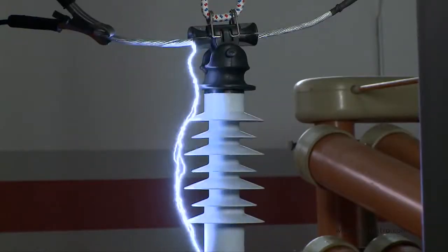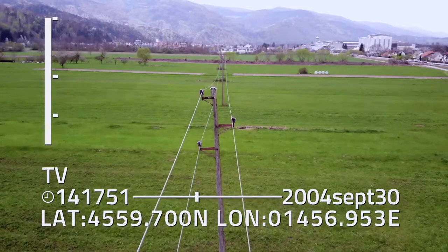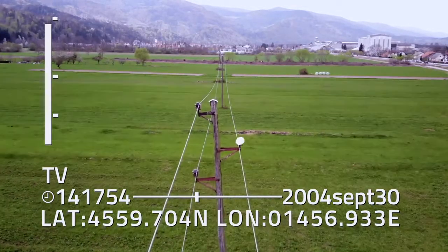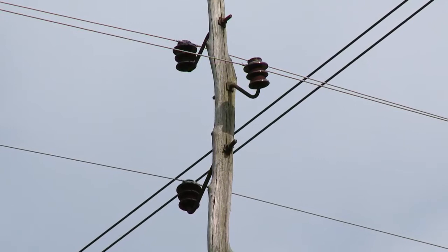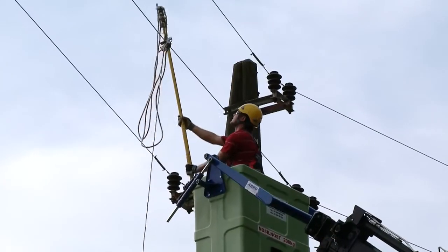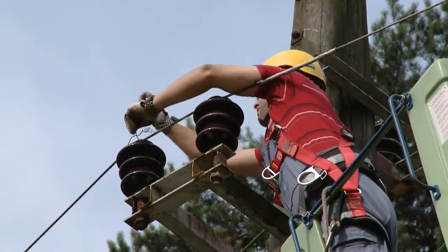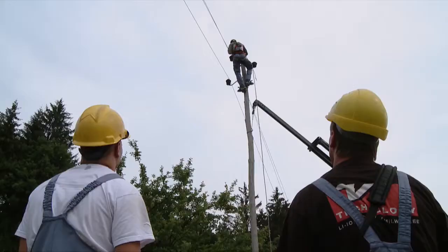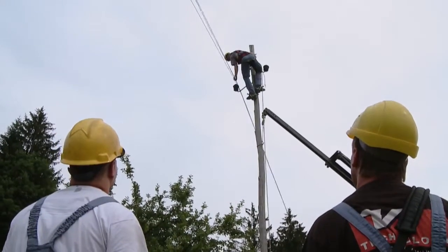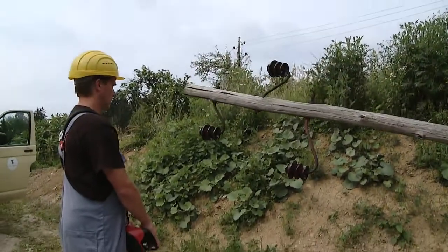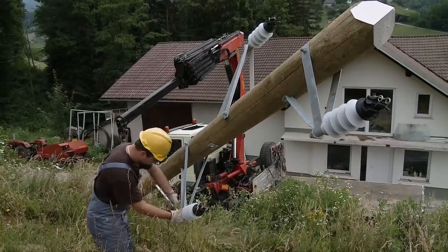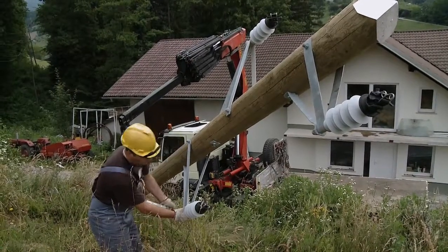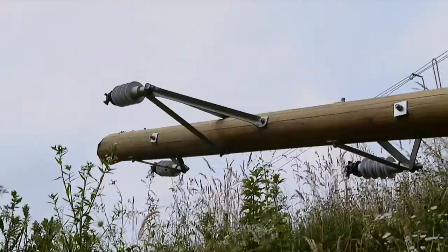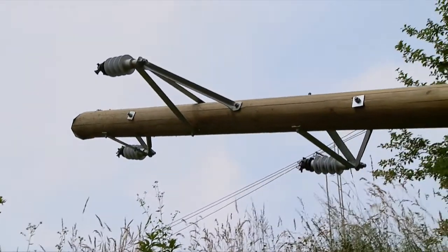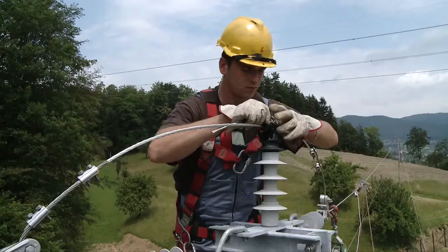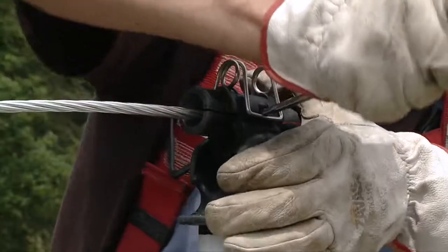Various studies, lab research, and measurements performed on overhead power lines have demonstrated that excessive electric field strength and resulting partial discharges are likely to occur at a bare conductor's fixation point onto an insulator with a metal end fitting. This may lead to the conductor burning off from its place of fixation after long-term use because of partial discharges. Izoelektro solved this problem by developing, patenting, and manufacturing post-line composite insulators with an insulated top-end fitting and a spring clamp with an insulating cover.